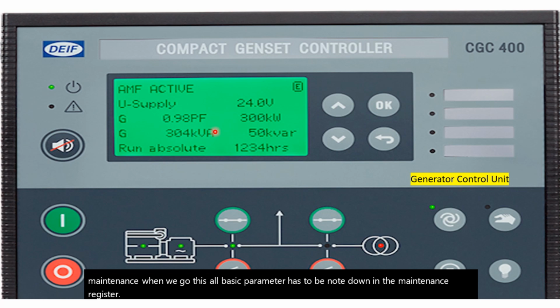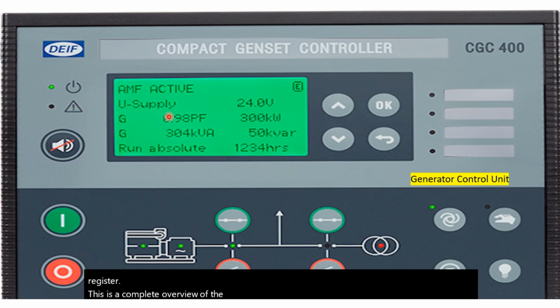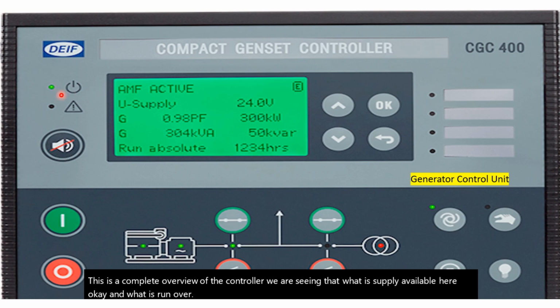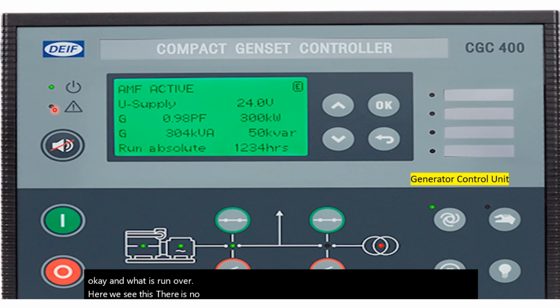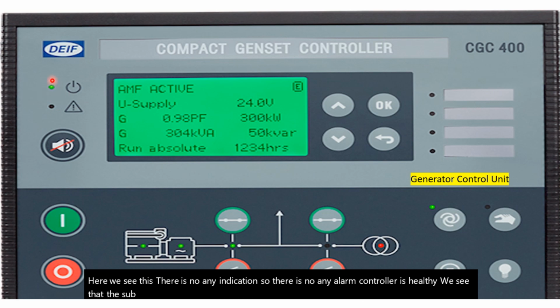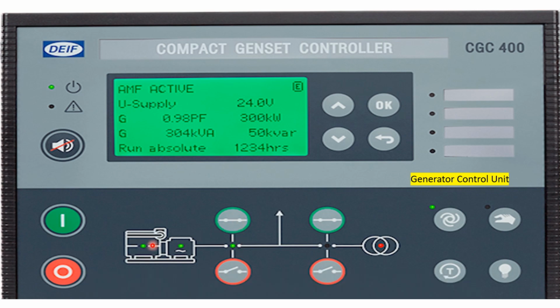This is a complete overview of the controller. We are seeing what supply is available here and what the run hour is. Here there is no indication, so there is no alarm. The controller is healthy. We see that the controller is on and its auxiliary supply is healthy. Here the generator is running, the engine LED is green, so the engine is running. This is the alternator, and from this single line diagram we see that the alternator is also running, and this is the generator breaker, which is also green. That means the entire plant is running on the generator.